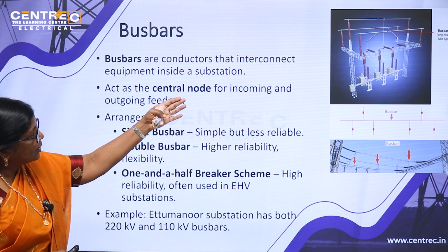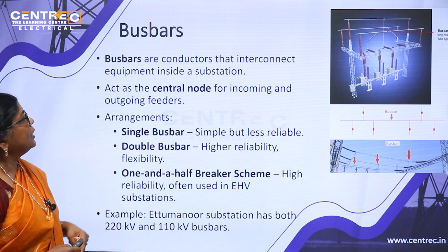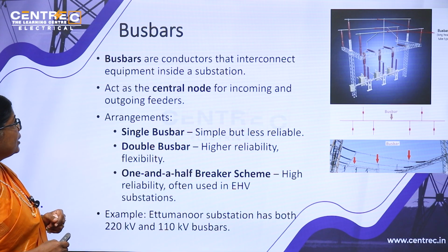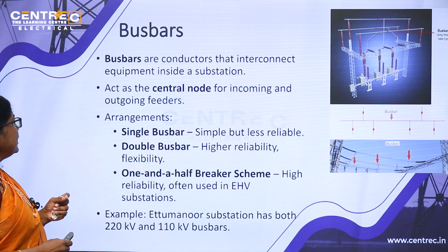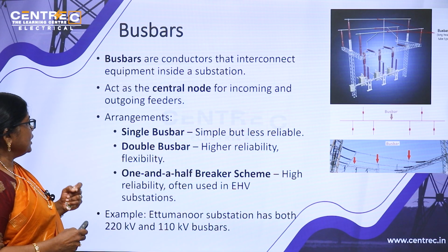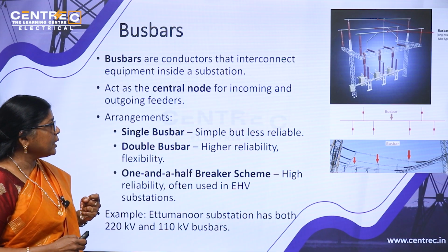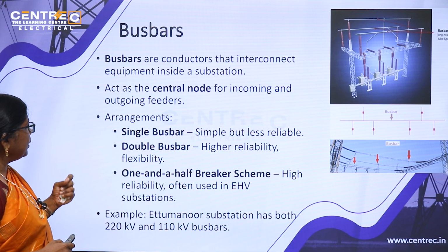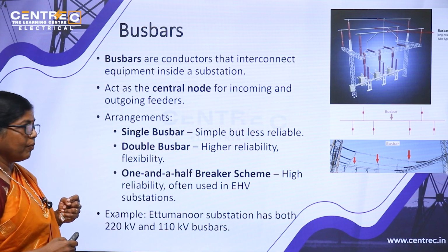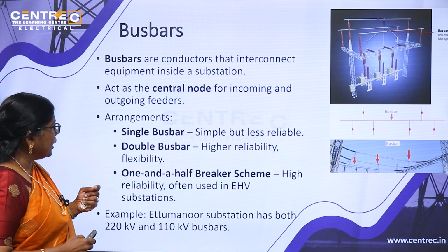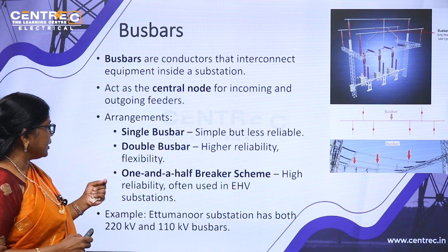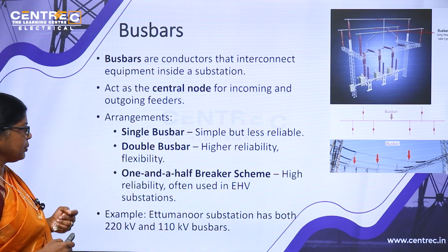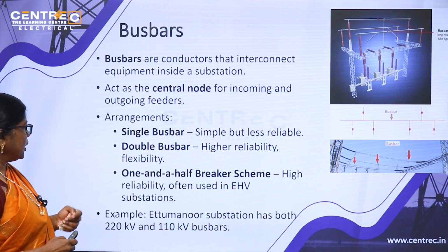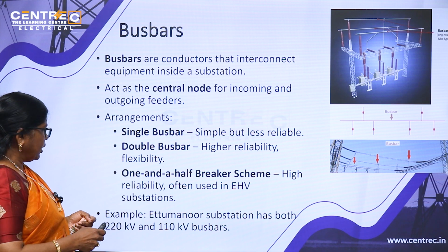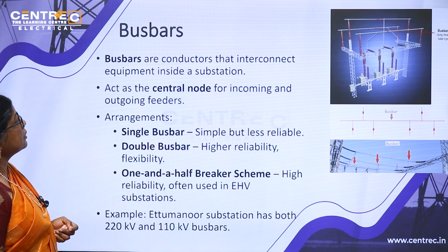Okay, we have seen on the right side the bus bar figure. It acts as a central node for incoming and outgoing feeders. Arrangements: single bus bar, simple but less reliable, and double bus bar, higher reliability and flexibility. 1.5 breaker scheme, high reliability, often used in EHV substations. A 2 substation also has 220 kV and 110 kV bus bars.